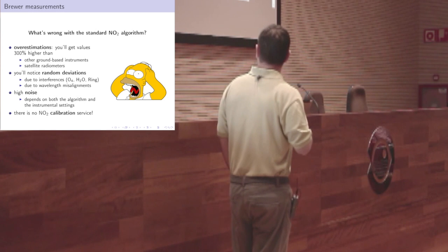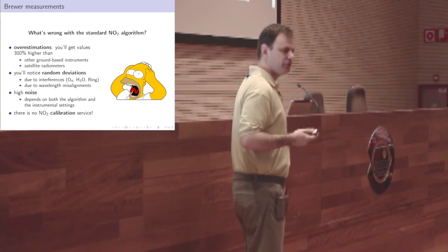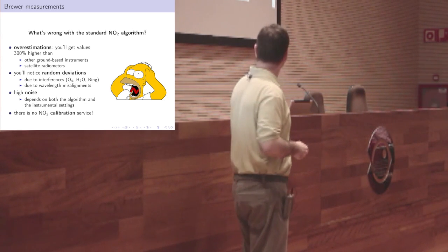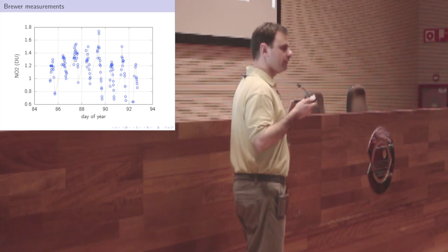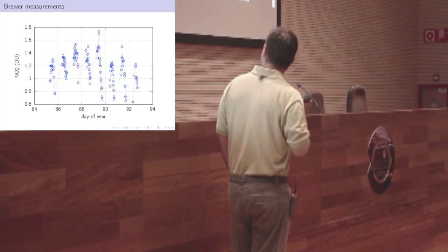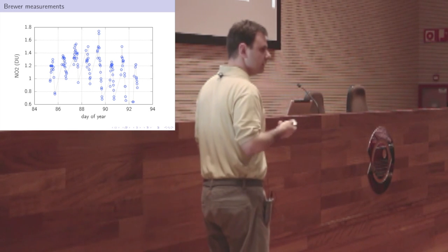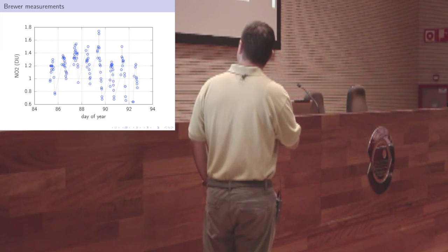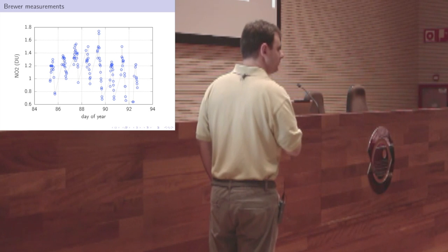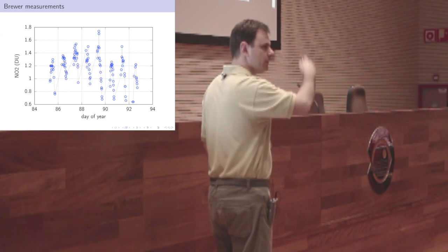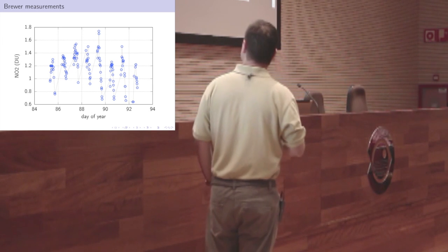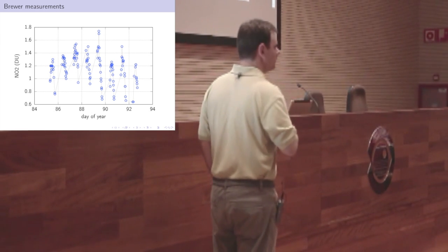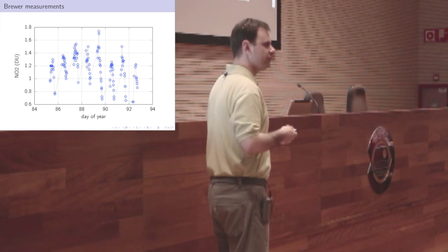And most of all, there is no calibration service by IOS or Kipp & Zonen for nitrogen dioxide measurement, as far as I know. So you will probably have wrong ETC constants. And this is the effect of wrong extraterrestrial constants. You may see each day an inverse U shape or a U shape, depending on the air mass, which is a clear sign of wrong calibration. You also see that those values are too high for the Aosta site, which is a semi-rural site.